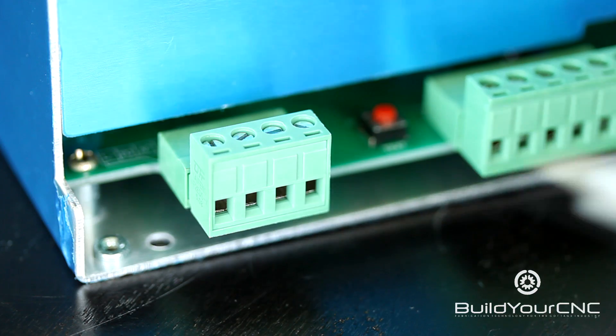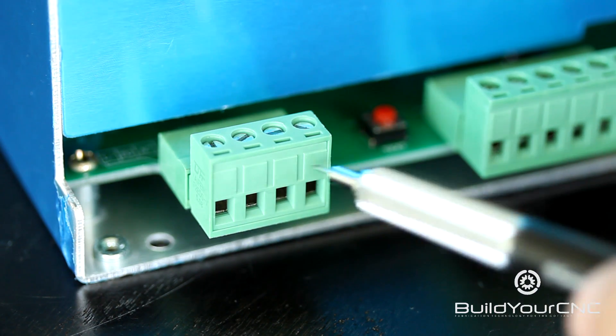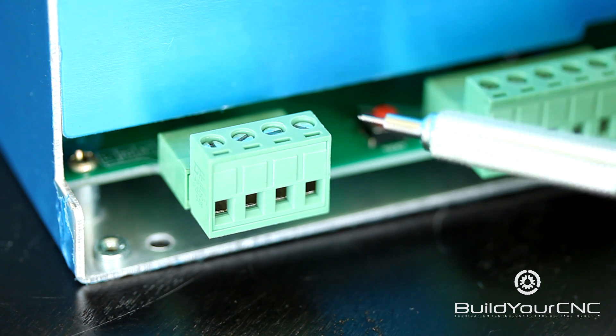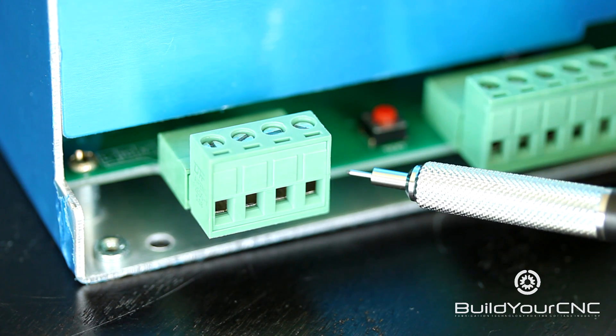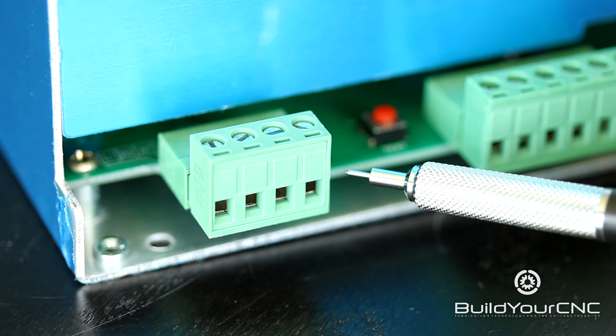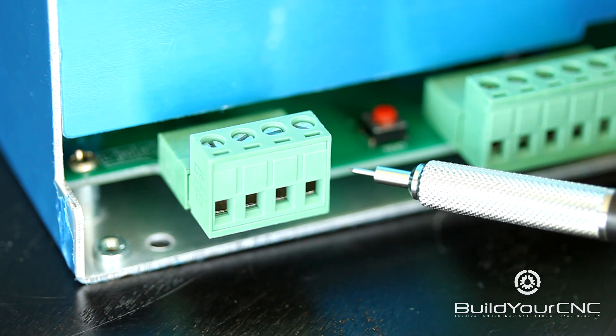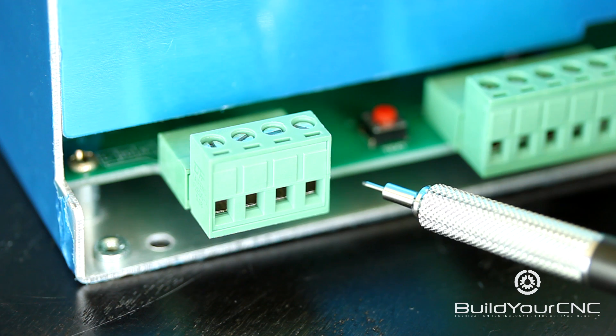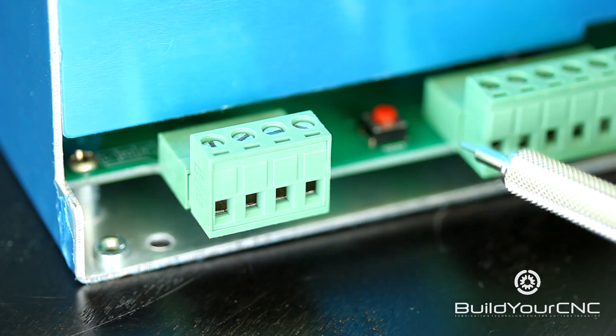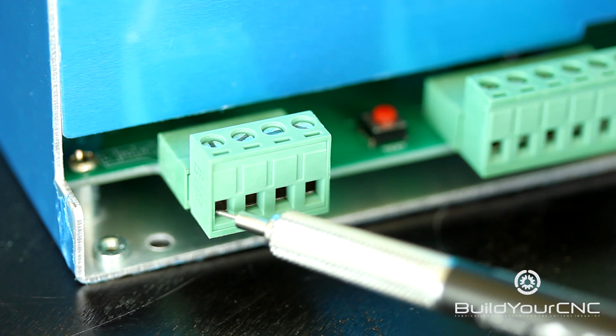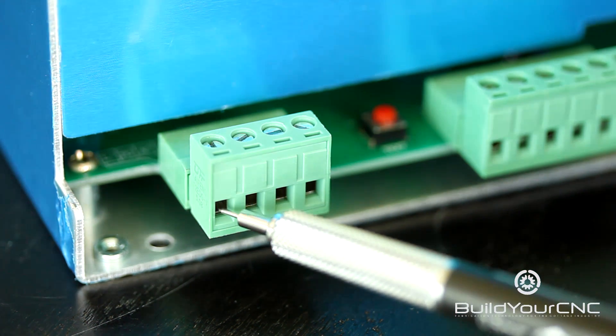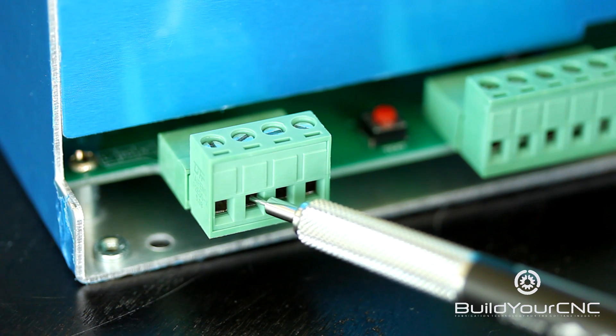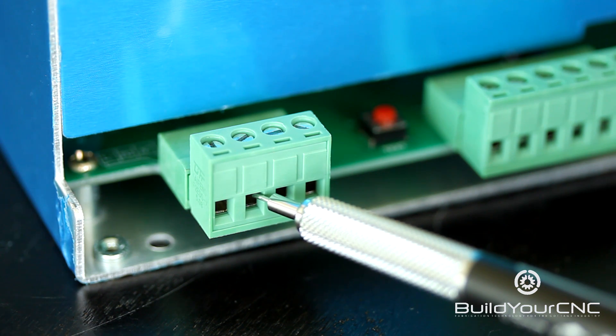The first bank of terminals are dedicated to the input for the power from the wall, from the mains, and the high tension return line. The first terminal is the high tension return line that is connected to the tube, and the next one is an earth ground from the mains.